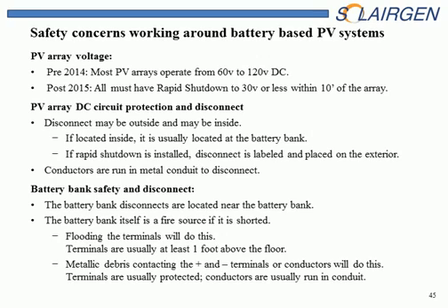PV array voltage pre-2014, most of them are going to operate somewhere between 60 to 120 volts. There's a few charge controllers out there that operate up to about 500 volts. They don't dominate the market, but they are there. So there is a possibility of high voltage DC coming in all the way to the garage or to the basement. Post 2015, all systems must have rapid shutdown that drops it down to 30 volts. So 2015 going forward, we have a lot of safety measures in place. It's prior to that we have a little concern.